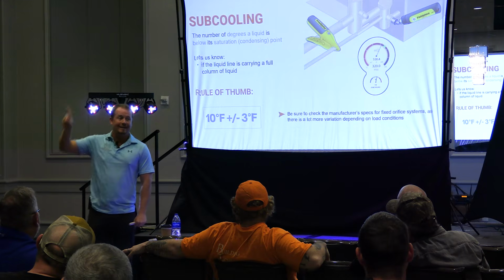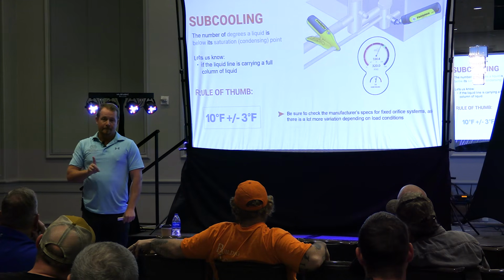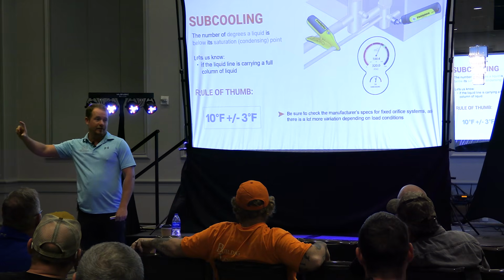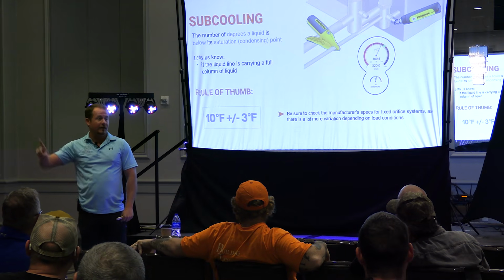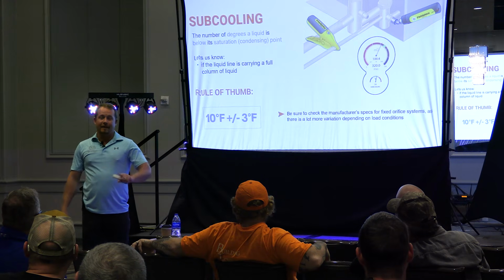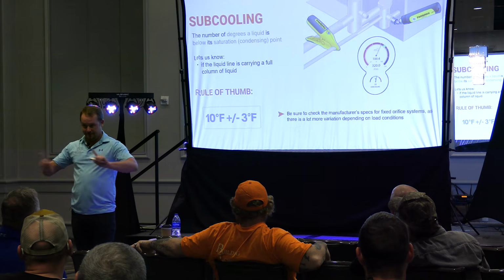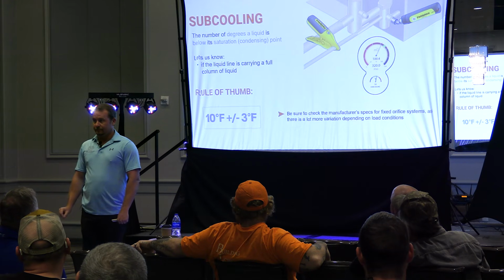device before it didn't. Meaning that if we had 10 degrees of subcool, we have 10 degrees of subcool, and now at the metering device, we've got 3 and we've got good liquid quality, versus having 5 degrees of subcool and now having flash gas at the metering device, yes, that is increasing efficiency.